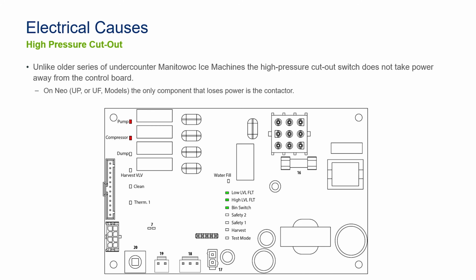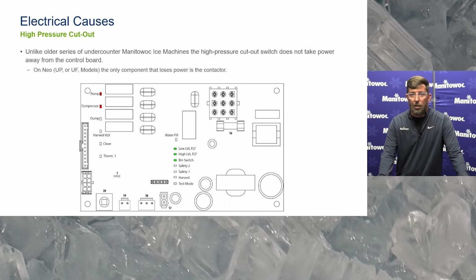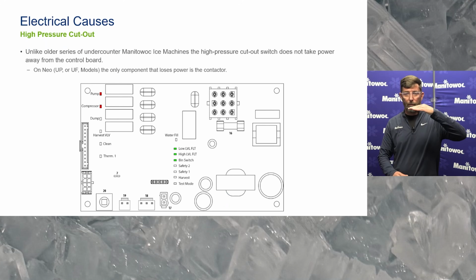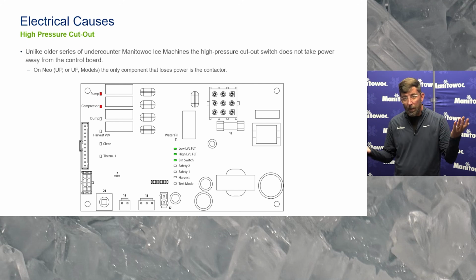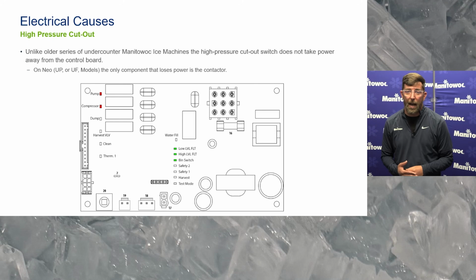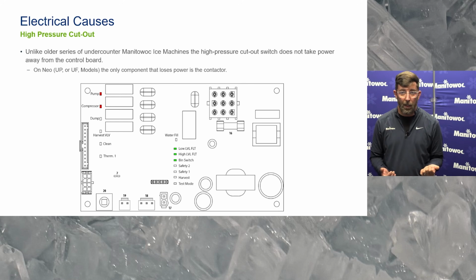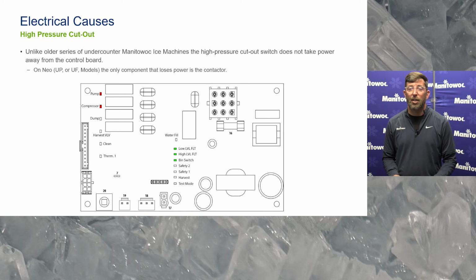The way I like to explain it when I'm teaching is, think of a bridge. Switch is closed, bridge is down. Switch is open, bridge is up. Well, this is electricity, and we can't go jump a bridge. So if the switch is open, all that's going to happen is the contactor is going to pull out, and it's going to stay pulled out until that switch closes. And at that point, the contactor will snap back in, and it'll keep running.